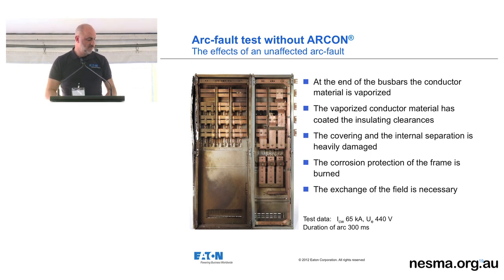Without an arc quenching system, the arc finds its way towards the end of the bus bars, it vaporizes, it burns holes through the side of the switchboard. The vaporized conductor material has coated the insulating clearances. All your internal segregations in that can be damaged as well. And then there's an exchange of the switchboard that needs to be necessarily facilitated.